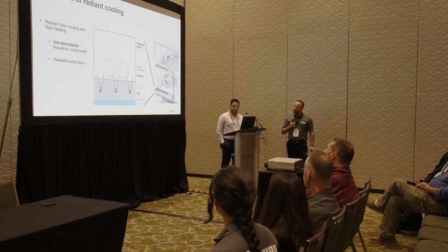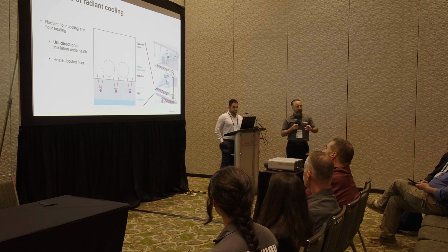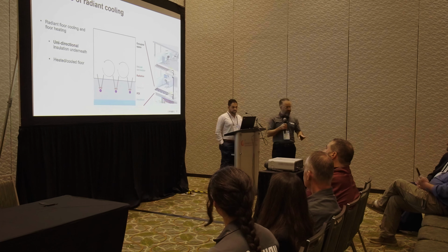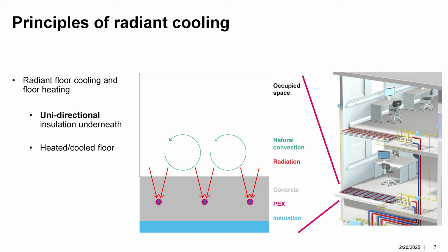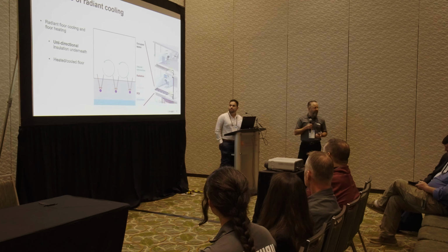How does the radiant cooling system work? It's the opposite way. We are trying to bring the temperature of the surface, especially the floor, down in a way that the other surfaces in the room, other occupants, other objects in the room start to radiate towards that colder surface. So this is a nice photo of a system. You see one side is insulated, on the other side the floor is cold enough. I'm going to talk about the temperature ranges and everything, but it's cold enough to absorb the heat from the bodies, from the surrounding area.